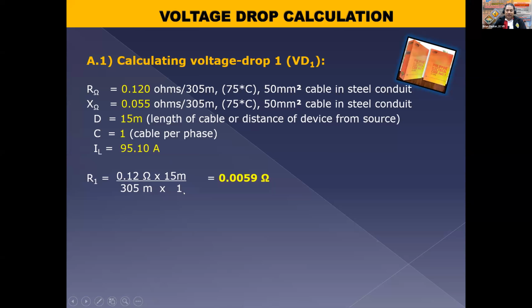So one cable per phase. Okay. Reactance same pa rin. We have to convert at 15 meters. So instead of 0.055, 0.0027 na lang. So maiksi na kasi, no?